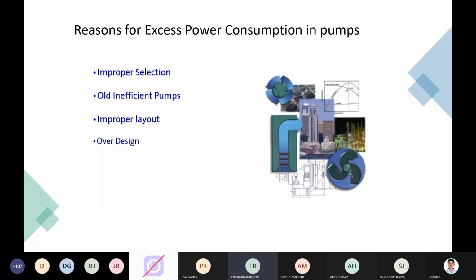So on the over design point, take an industry which has an ambitious plan to expand at a later date. If they have accommodated something on the pumps for the future, they would be operating at maybe partially open or 25% open of the discharge valve. Definitely we can say at the moment it is an over design, because it is not going to support the current situation, and obviously it will be operated at very low efficiency. So these points we will elaborate in the coming slides.